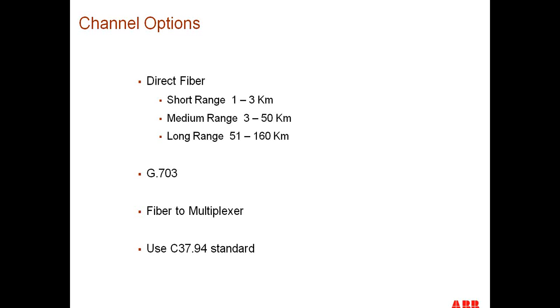Another communications channel that is being used quite successfully is the G.703, or you could use a fiber into a multiplexer rather than using a dark fiber. All of these could use the C37.94 multiplexer standard, which is a standard for interfacing between the IED and the multiplexer.